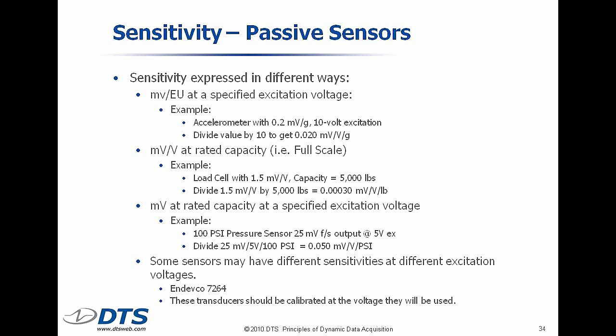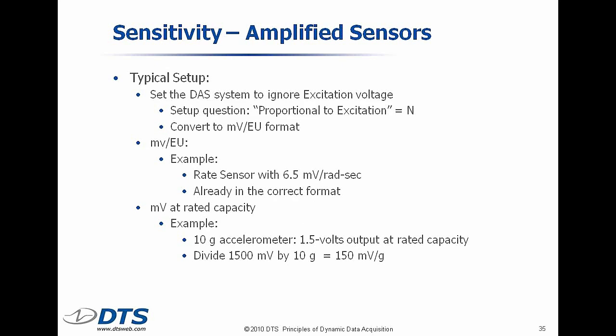Now, the same thing holds true for amplified sensors. As we discussed, amplified sensors are generally not proportional to excitation, so the first thing you need to do is tell the system that it's not a bridge, and then you need to get sensitivity into what we call the millivolt per engineering unit format.